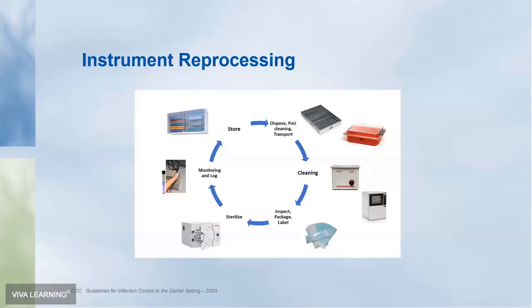The reprocessing area has to have a unidirectional workflow. So when everything arrives, when you take it through from transportation to the receiving area, that's obviously the dirty end or the contaminated end. It would then flow through each of these stages. So the instruments would then move along the line within the room from dirty to clean, being cleaned, then inspected for damage and to check they're clean, for packaging and labeling, for sterilization, after which they are sterile, provided they are in intact packaging that was not taken out of the sterilizer before it was dry.